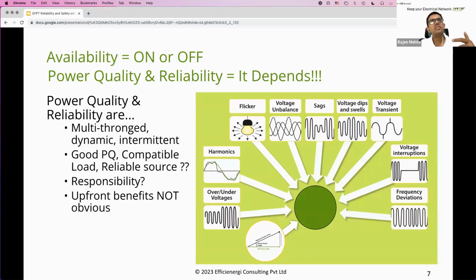Most reasons for voltage sags are due to utility-level changes or reclosing transmission line faults. These are most of the reasons voltage sags occur. Within a premise or facility, voltage sags occur due to large motor starting and so on, as you mentioned. But more often than not, these are due to utility-side faults, phase-to-line, line-to-line, or line-to-ground faults, and different kinds of faults occurring.